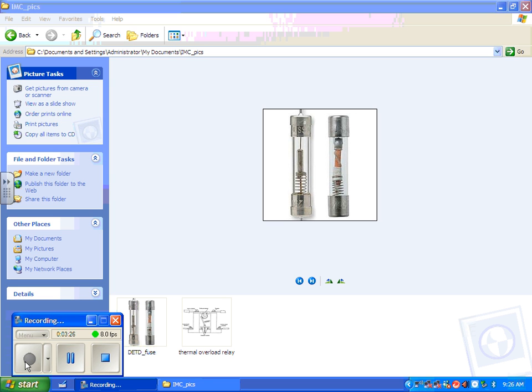In allowing that, it's a big, say, a tsunami of electrical current. It's not a tsunami, but it's a big wave of current that's rushing in. As we talked about, the induction of the motor builds up and slows down the current flow. So it only happens for a second or so, and we want to allow that. Dual element time delay fuses do that almost better than anything else. So we want to allow that.